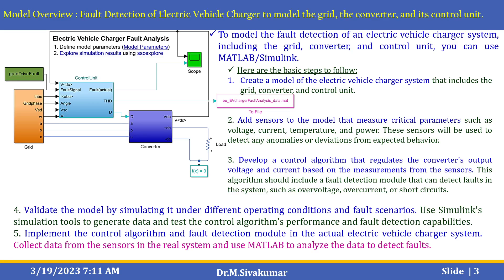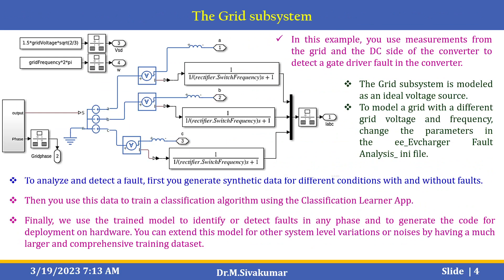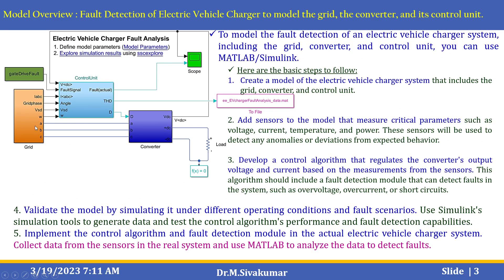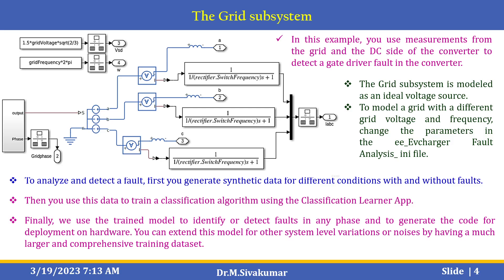Finally, implement the control algorithm and fault detection algorithm with accurate values. You need to send the files to scope and collect data from sensors in real systems. MATLAB is used to analyze data to detect faults. If you double click on a block, you can get the grid subsystem. You can also double click to get the converter subsystem. In this example, we use measurements from the grid and DC side of the converter to detect gate driver faults in the converter.